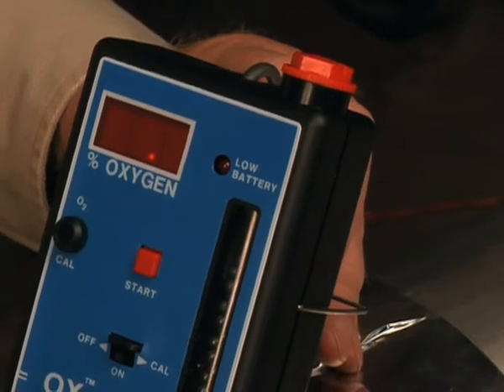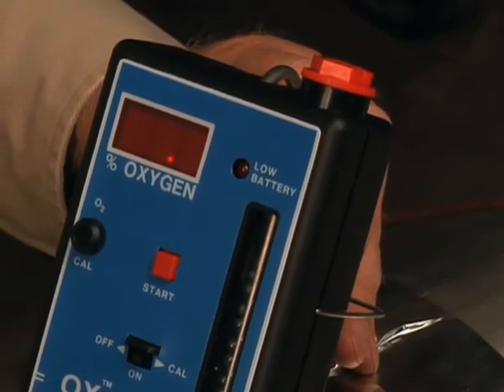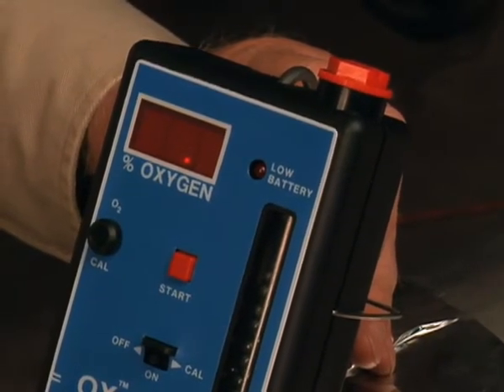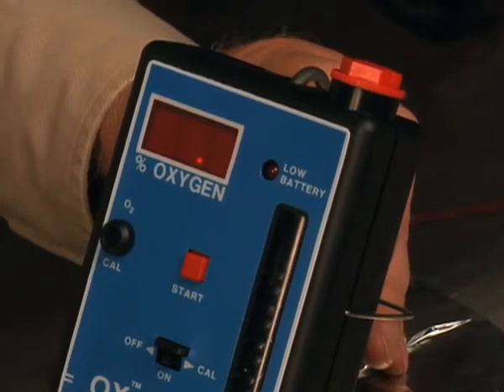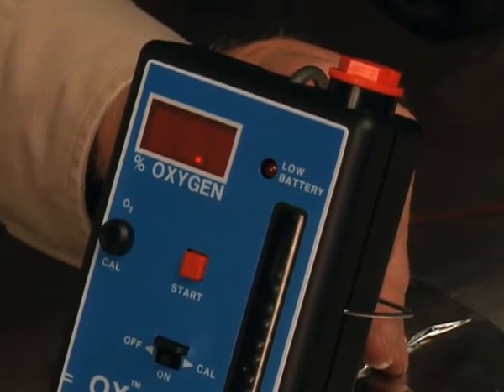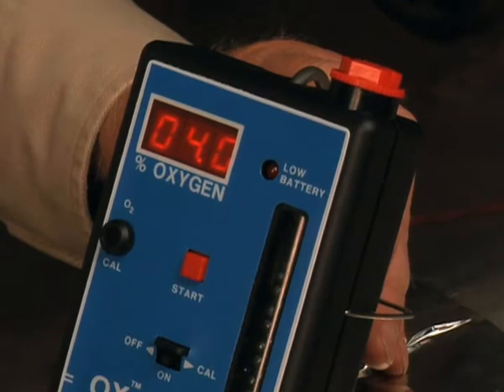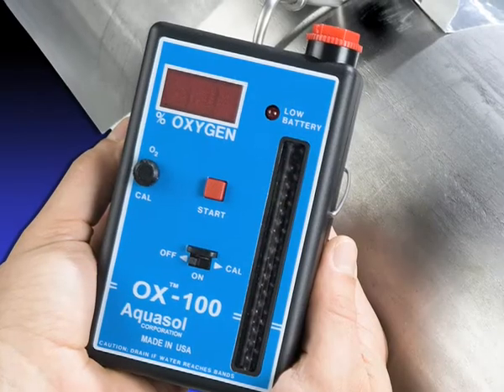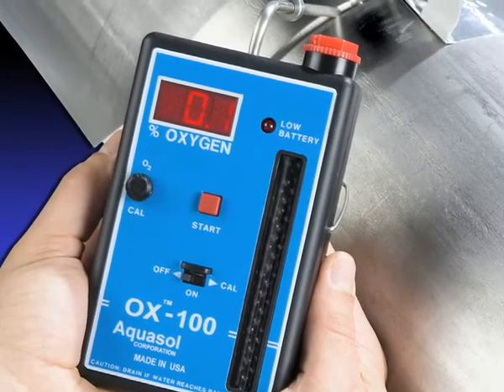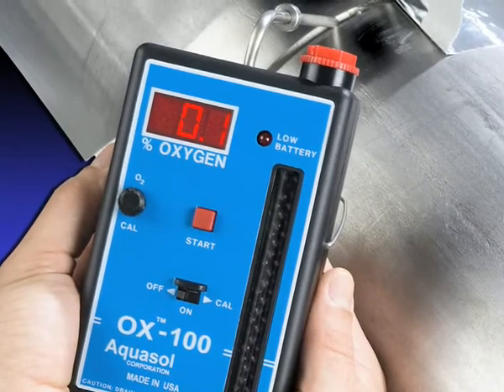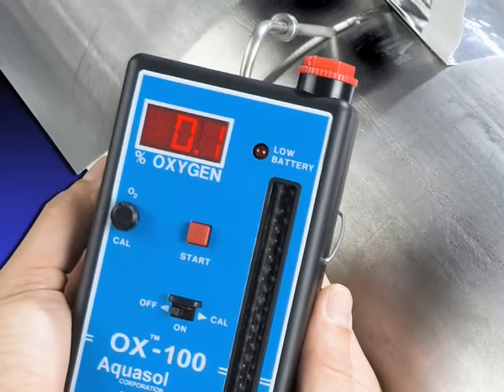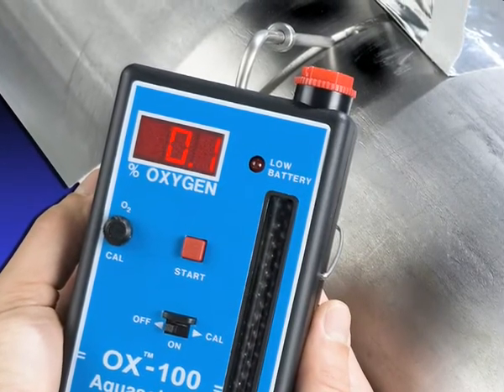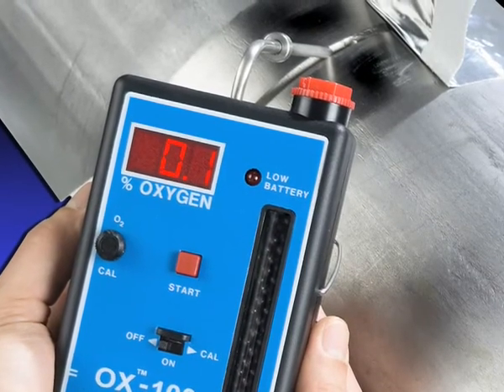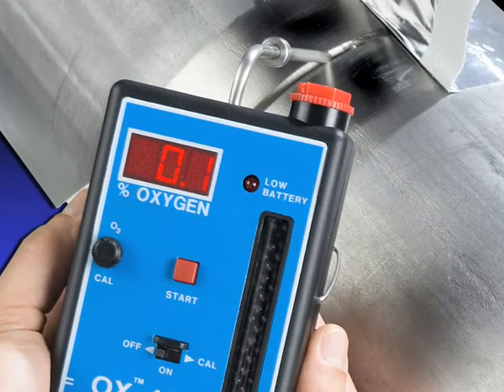Once the Start button is depressed, there will be no oxygen reading displayed while the monitor draws the sample. After 30 to 60 seconds, the reading will appear on the digital display panel showing current oxygen levels. Once the desired oxygen level is met and the reading is displayed, record the oxygen reading if required or desired. It may take several samples before the desired reading is achieved.